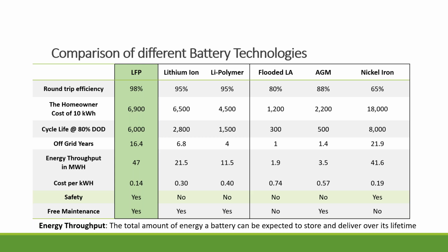The cost here is just what you find if you go to a website and search for the different battery chemistries and how much you're going to pay for them. Then on the lifespan, assume that all the batteries are discharged every time at 80%. By the way, with the flooded lead acid family, you still can discharge 80%. You can, but of course, you can see that the cycles really wouldn't last too long. That's why typically when you design lead acid, you set up a 50% DOD. But I would like to get an apples-to-apples comparison, that's why I set it at 80%.